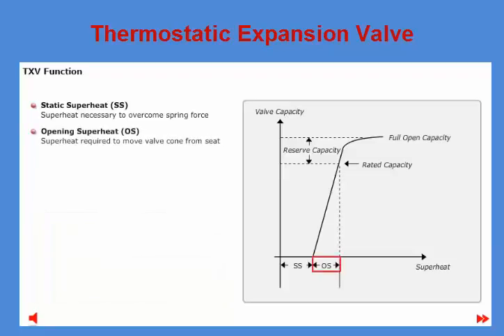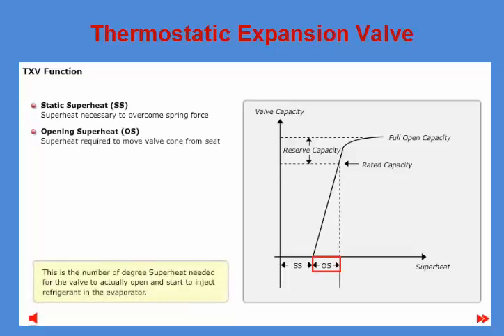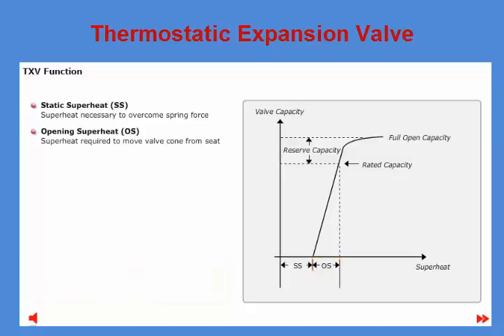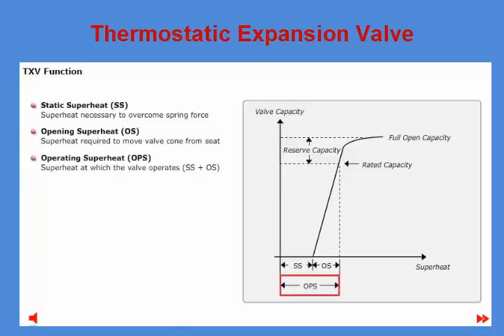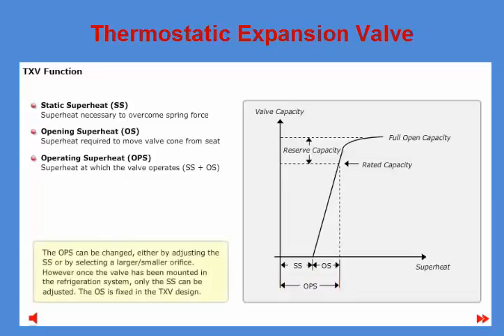The second part is the opening superheat, or OS — the number of degrees of superheat needed for the valve to actually open and start injecting refrigerant into the evaporator. The combination of the two superheat values is referred to as operating superheat, or OPS, or total superheat. This is the value the customer or fitter can measure on their refrigeration system. The OPS can be changed either by adjusting the SS or by selecting a larger or smaller orifice. However, once the valve has been mounted in the refrigeration system, only the SS can be adjusted; the OS is fixed in the TXV design.